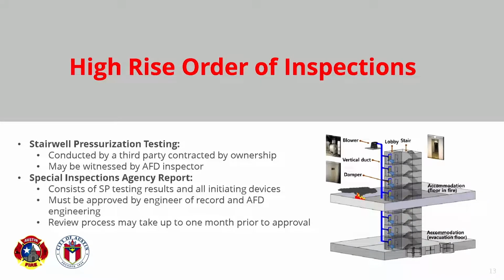The Special Inspections Agency report - this is going to be very important to you closer to the end of your project. This is the report generated by the company who does your stairwell pressurization. The entire report consists primarily of the results of the stairwell pressurization after it's been adjusted, and every single initiating device that starts the stair press fans. So you're looking at smoke detectors, water flow devices - that's pretty much it, but there's a lot of them. Anywhere you've got a smoke detector or a water flow, which you're going to have at least one water flow device on every floor, all of those items have to be tested by me.